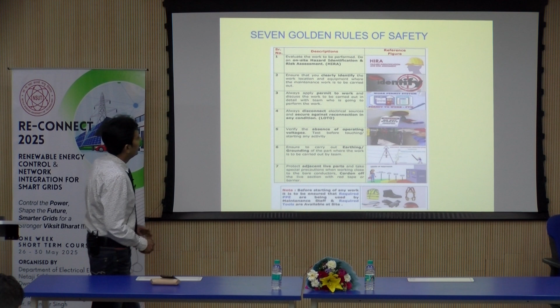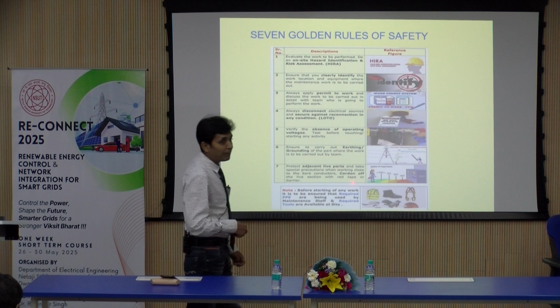There are 7 golden rules of safety wherever you are working. It starts with HIRA — you have to identify the hazard, then do the risk assessment of the site. You have to clearly ensure and pinpoint the work location and equipment where the maintenance work is to be carried out. You have to ask for the permit to work, then apply LOTO. Then you have to ensure there is absence of operating voltages before starting any work. You have to do proper grounding, and ensure there is no adjacent live part. Last but not least, you have to use proper protective equipment before starting any work in the system.